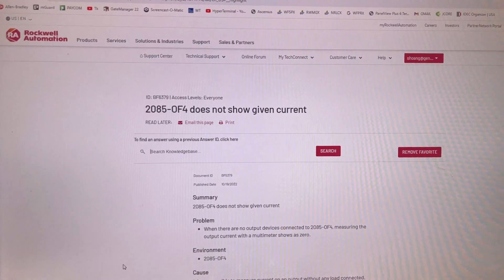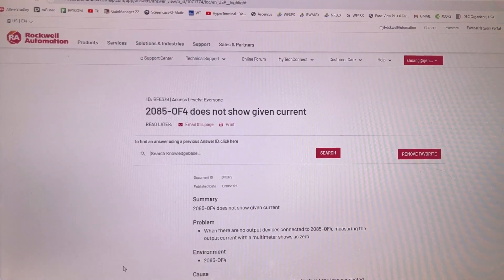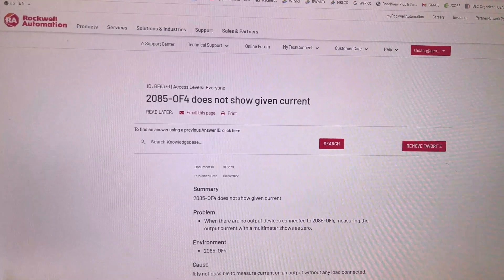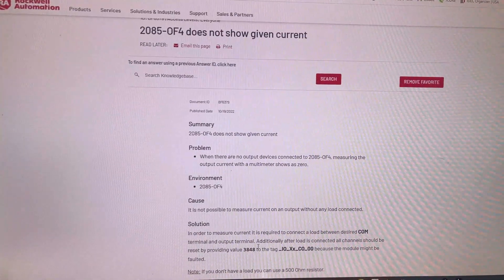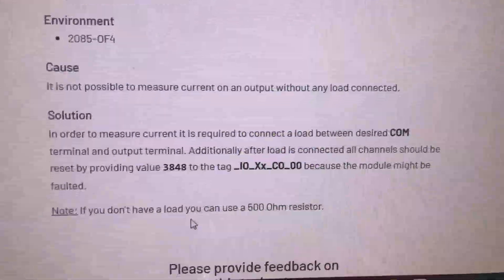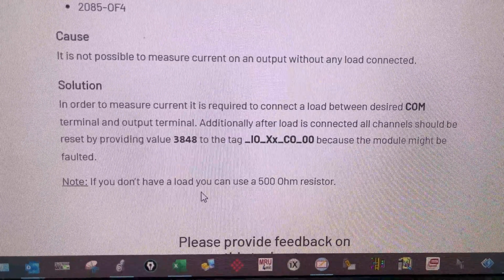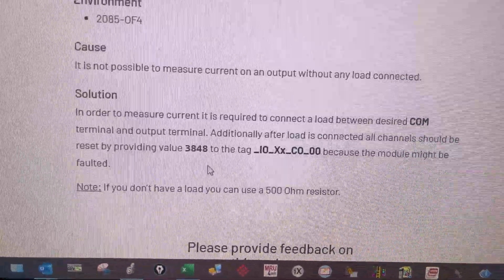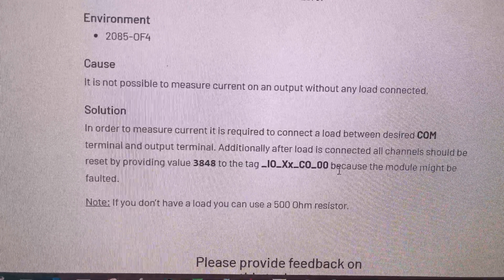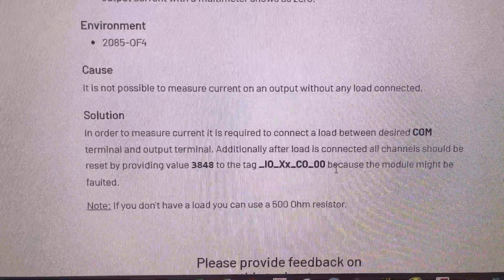This is the solution from the Rockwell Automation Knowledge Base Center. We need to write the value 3848 to this tag in order to reset the analog output channel.